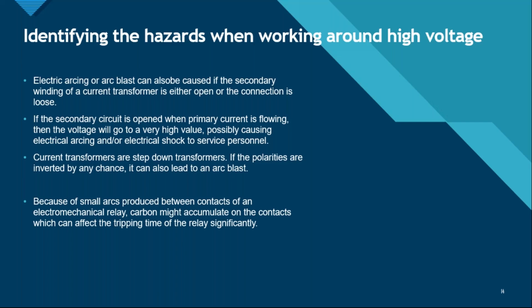Current transformers are step-down transformers. If the polarities are inverted by any chance, it can also lead to an arc blast, right? In case the polarities are not mentioned, in case the primary and secondary windings are not marked, and the polarities are reversed while the current transformer is being connected, there can be high current produced on the primary side, and that can also lead to an arc blast.